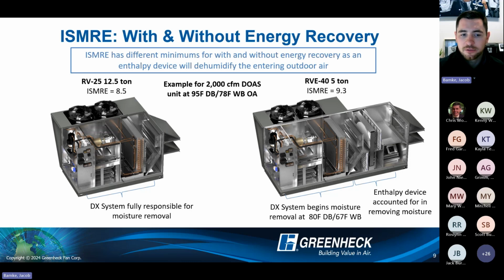a DX system that is fully responsible to remove all the moisture. When you add energy recovery on, that's a total enthalpy device. So it actually reduces your moisture content as well before it enters the DX system. So even though it's really humid outside, I'm taking a lot of that humidity out with my energy recovery device. So now my system doesn't have to work as hard, which means I don't have to spend as much energy on the same exact CFM. And that's where your efficiency values are changing a little bit.